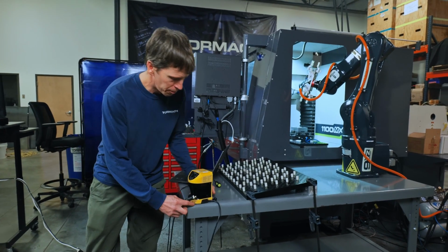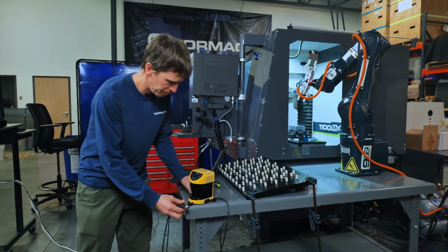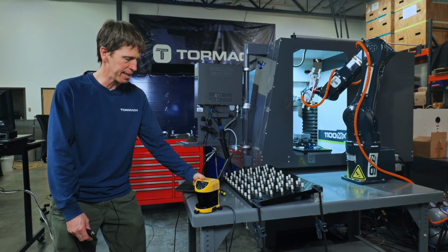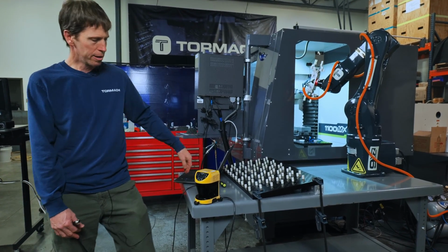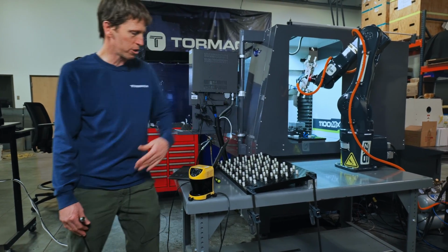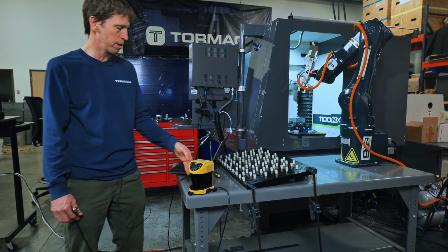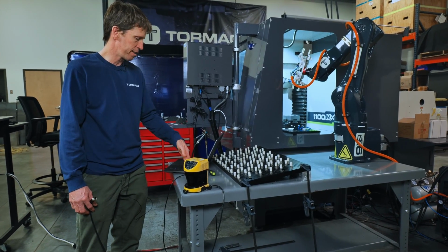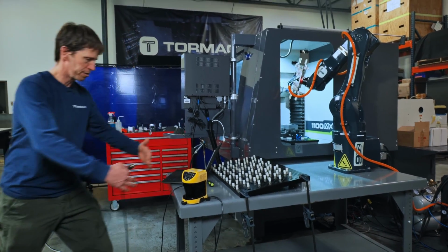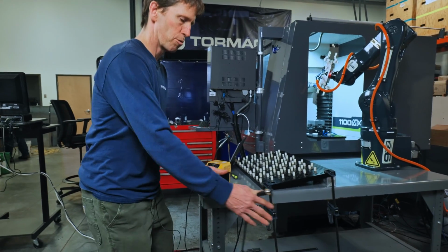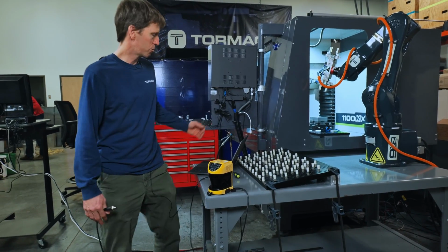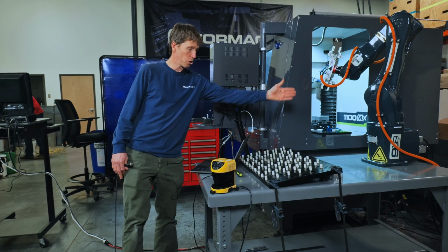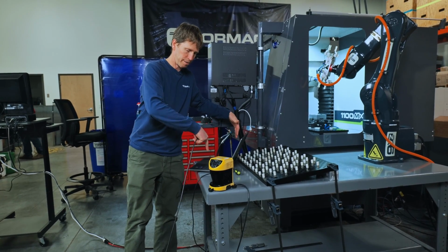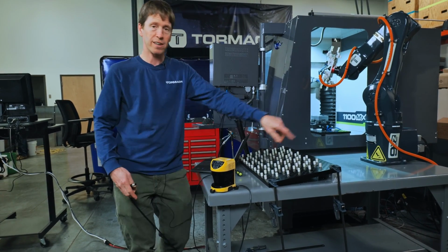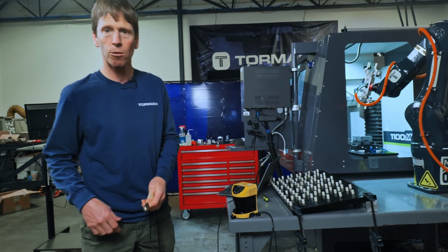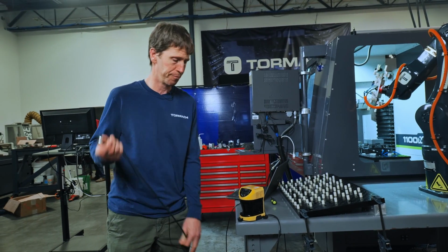You'll notice also that it will create a plane in about 270 degrees of direction. So the way I've got it oriented here, it will be safe for anything that comes towards the robot from this side, anything that comes towards the robot from that side. But of course, you could sneak in through here and it wouldn't know, because that's not part of that 270 degree protection. We'll see that a little bit later when we get into the configuration software.